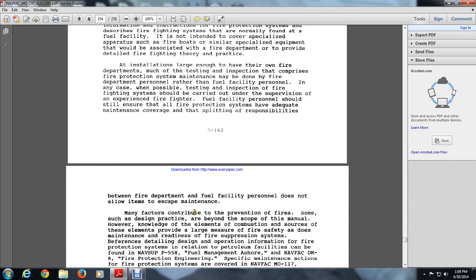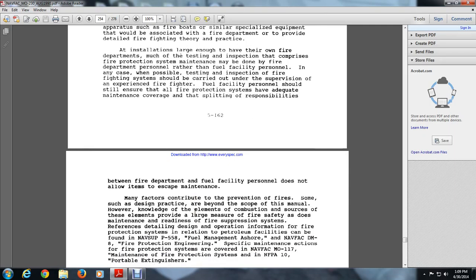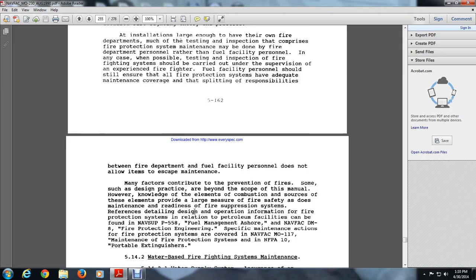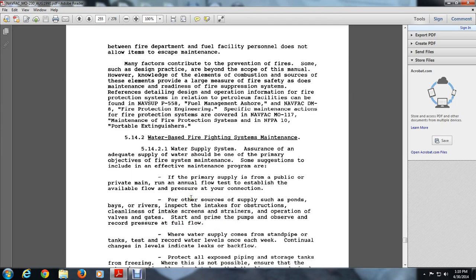Many factors contribute to the prevention of fire. Some design practice, are beyond the scope of this manual. However, knowledge of the elements of combustion and any source of these elements provides a large measure of fire safety, and as does maintenance and readiness of fire suppression systems. Reference and detailed design and operational information on fire protection in relation to the petroleum facility can be found in NAVSUP P-558 and the Fuel Management Ashore NAVFAC DM-8 and Fire Protection Engineering. Specific maintenance actions for the fire protection system are covered by the NAVFAC MO-117, maintenance of the fire protection system, and NFPA 10 portable extinguishers.